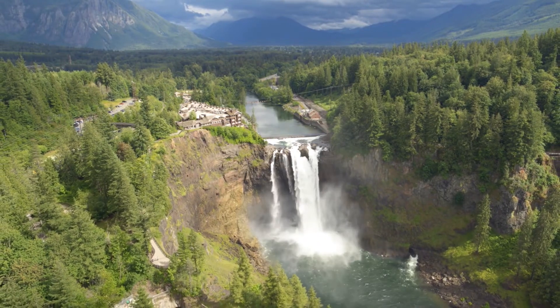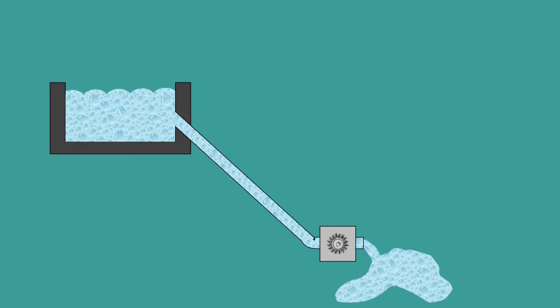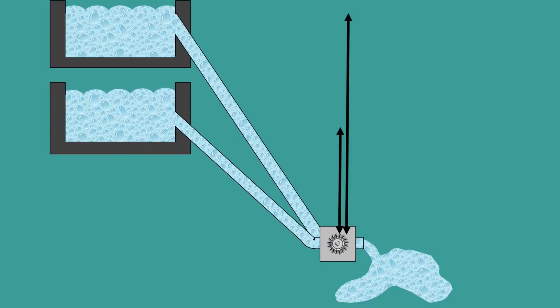Technically, this height is called the head and the volume of water is called the flow. In hydropower plants, head represents the vertical distance between where water enters the hydro system and the location of the turbine. The more head you have, the more power it will generate.